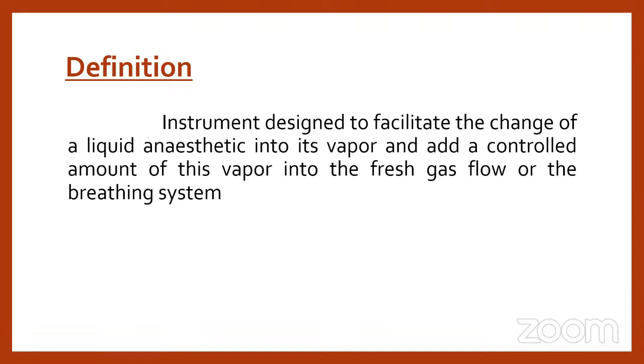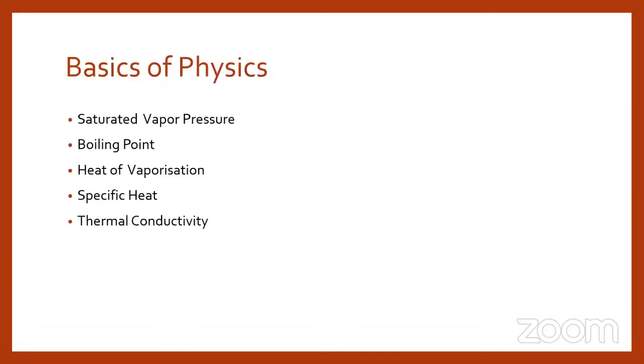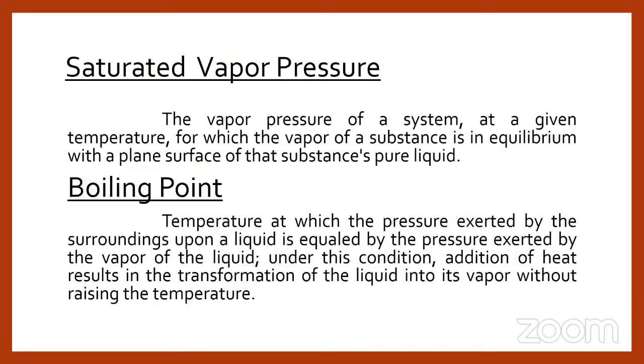Whenever the fresh gas flows through the vaporizer, the main aim of the vaporizer is to provide some vapor of anesthetic liquid which is already stored in the vaporizer container, and that vaporizing agent, the anesthetic agent, will mix with the fresh gas, and it will be inhaled by the patient. It will be delivered to the patient through the tubes. And to understand this, we have to know a little bit of basics about saturated vapor pressure, boiling point, heat of vaporization, specific heat, and thermal conductivity. I'm going to elaborate these things in detail.